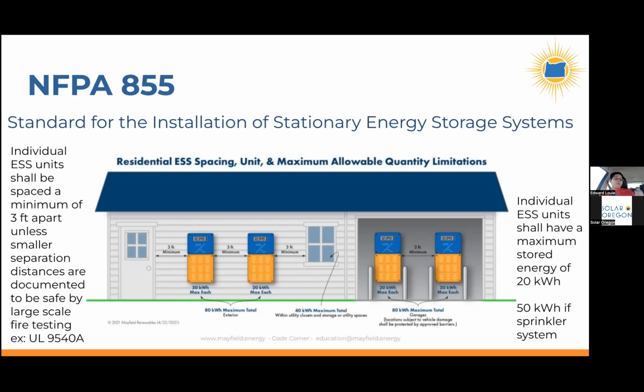And then there's also a caveat in this as well, where if you have a room that is sprinklered, then you're allowed to put up to 50 kilowatt hours per area, and then space that 50 kilowatt hour 3 feet away from the next 50 kilowatt hour, up to the 80 kilowatt hour maximum or the 40 kilowatt hour maximum. So I guess that 50 kilowatt hour maximum would really only affect you if you were putting it in a garage, because look at this requirement. If it's inside, you're up to 40. So that doesn't really apply.